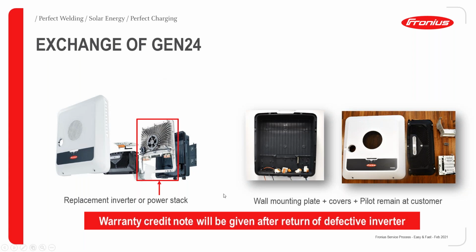For exchanging Gen 24, it's the same. You have to retain the front cover, the DATCOM cover, and the pilot, and also the wall mounting sticks. As you see in the right hand side picture, these things stay with your customer. So these things you will not exchange. Whenever you are exchanging, you will exchange the power stack.